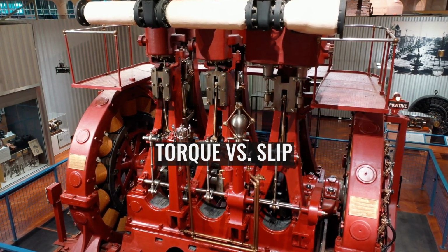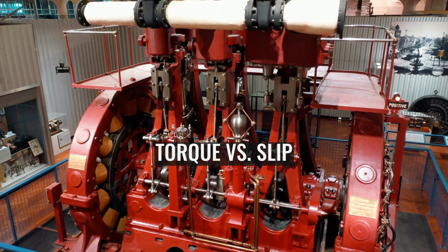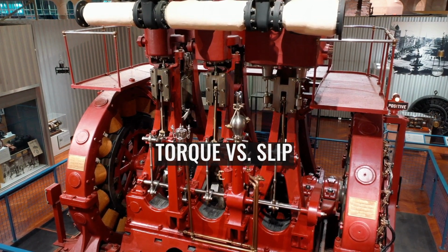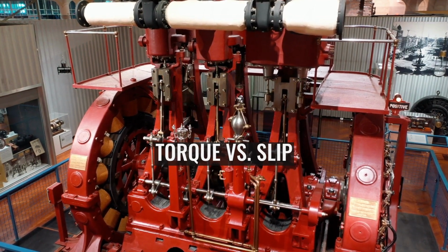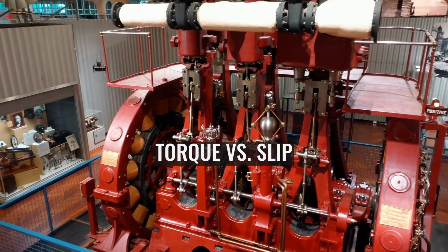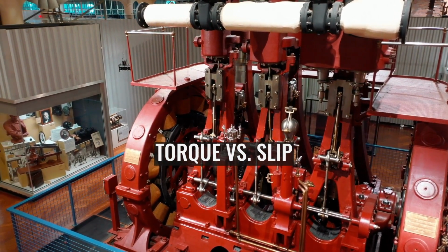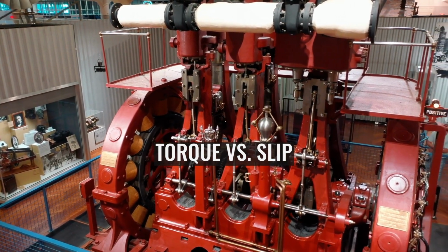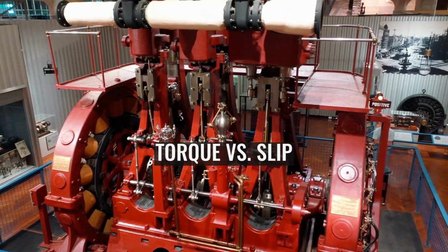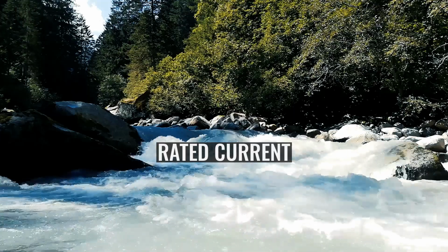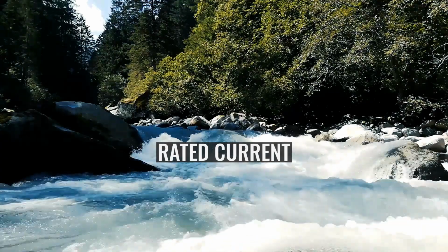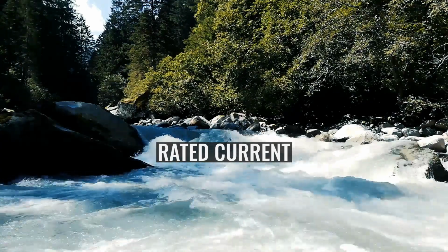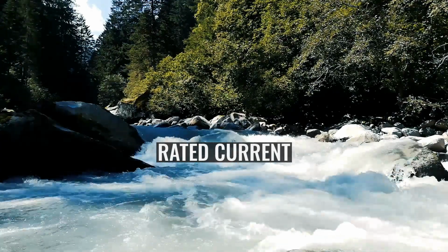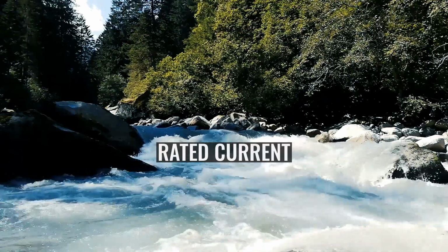As the speed of the motor increases, the counter torque reaches a max value, the breakdown torque, up to which it can operate before the operating conditions become unstable. Ideally, induction generators work best in the stable region between the no load condition and maximum torque region. Rated current. The maximum power that can be produced by an induction motor operated as a generator is limited by the rated current of the generator's windings.